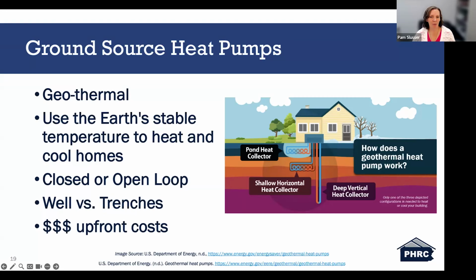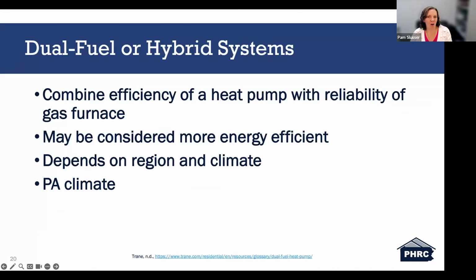The other thing that could come with these, additional permits might be required depending on the location for running the in-ground loops. So it's always a good idea to check with local zoning requirements to see what is required in that municipality or area. And then we have our dual fuel or hybrid systems. These systems combine the efficiency of the heat pump with the reliability of a gas furnace. They're made up of both an electric heat pump and it could be a gas furnace or propane. It all depends on what it is.